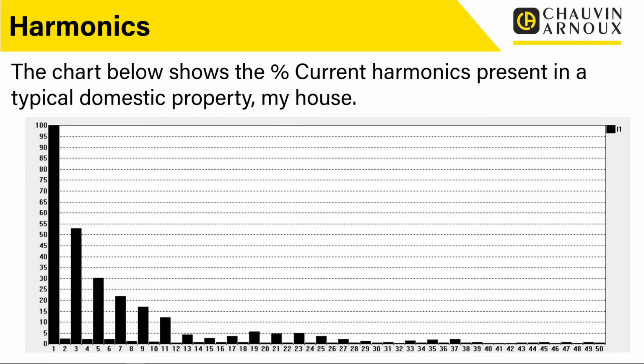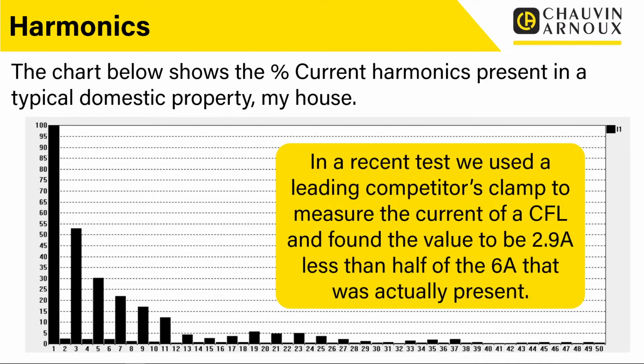So you can see here that if we've got a harmonic clamp meter that measures up to the 25th harmonic, we will capture all of that current. Whereas if we're just using a clamp meter that's filtered just to measure the fundamental frequency, then we're not going to pick that up. Now, we recently did a test, and there's a YouTube video, I think, knocking around about this.